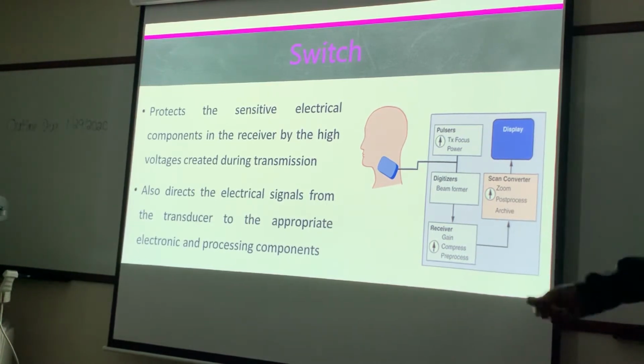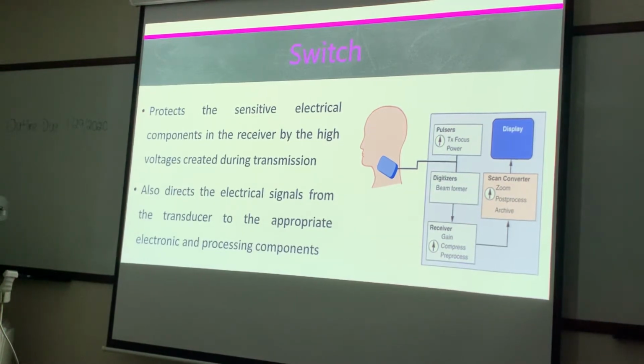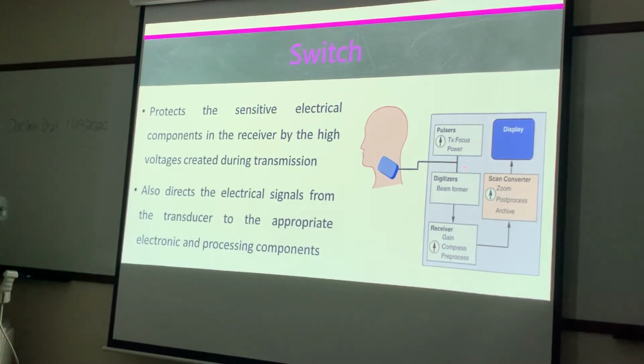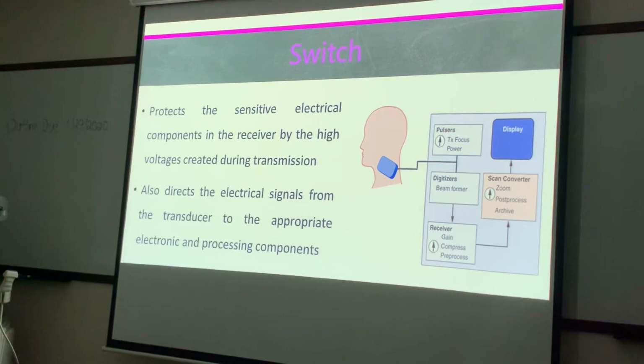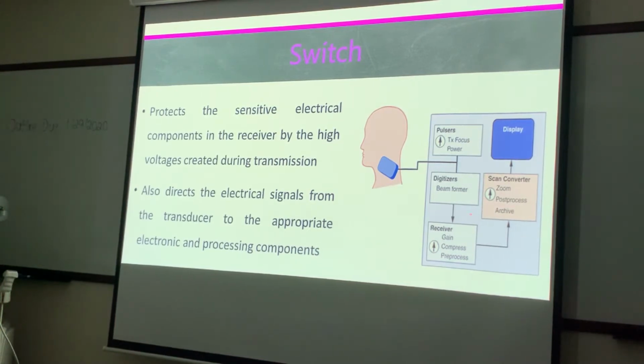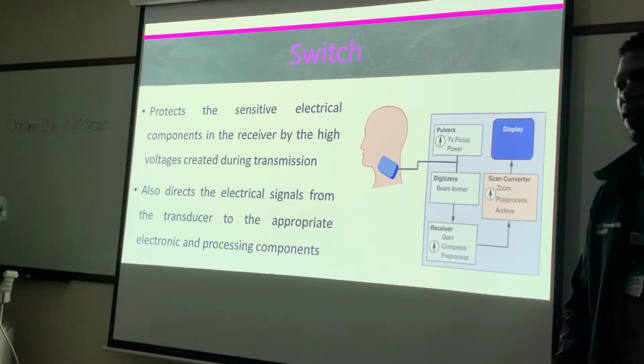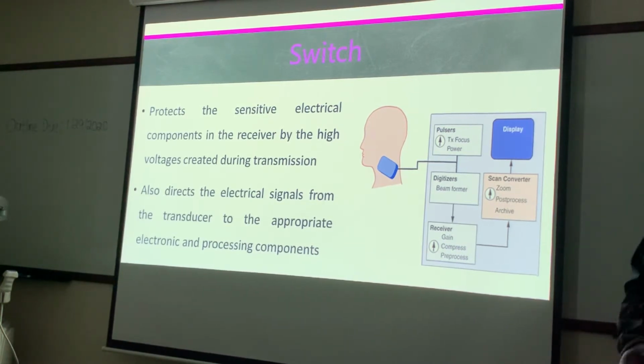It also directs the electrical signals from the transducer to the appropriate electronic and processing components. Meaning that our signals won't just go back to the pulser. It's going to close that channel off and let that signal come back to the beamformer, to the digitizer, or to the receiver. But most importantly, know that the switch in the beamformer protects the receiver from those high voltages, and it functions during transmission and reception.